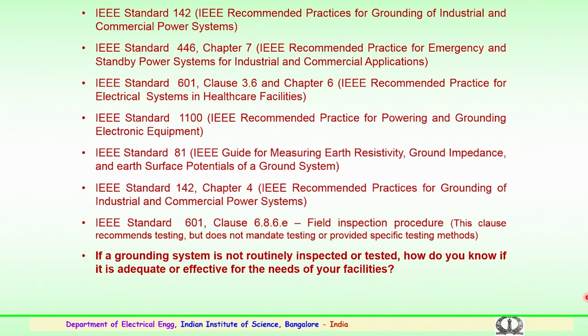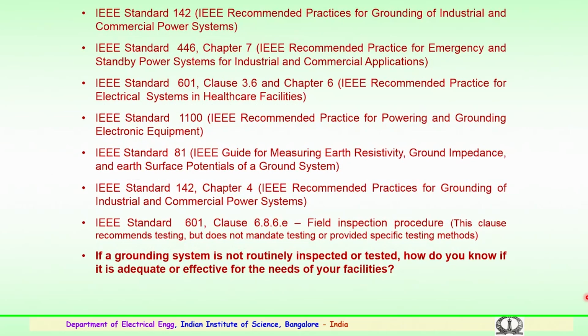And apart from the standards, it is important that if any grounding system is not routinely inspected or tested, it is difficult to know if it is adequate or effective for the needs of the facilities which are to be tested. So, proper inspection and proper testing have to be conducted routinely for the grounding or earthing systems. So, that concludes the planning of the high voltage laboratories, and the importance of the standards which have been suggested. So, thank you.